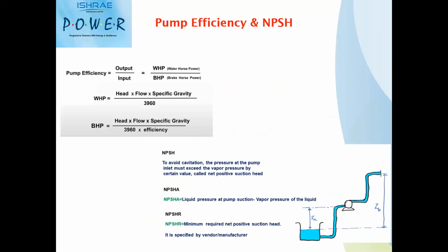So two points which I want to highlight for any particular pump selection or pump parameters: one is efficiency. Whatever pumps we are selecting or whatever specifications we are getting in the market for typical pump requirements for HVAC, we are defining efficiency. We have flow and head. Flow is calculated based on your chiller capacities, or in case of your secondary pump, based on your installed load capacities, you are arriving at your primary and secondary pump flow rates. And in a similar way, in cooling tower application, based on your cooling tower load, you will be arriving at cooling tower condenser pump flow and head. So you have basically flow and head parameters in your hand.